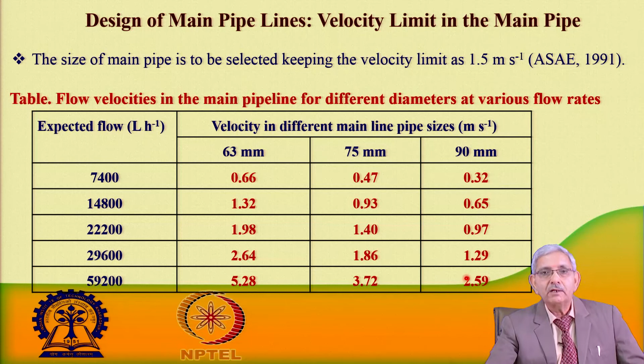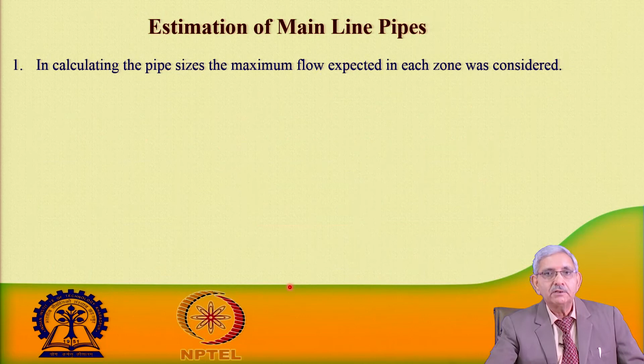For the 63 millimeter pipeline, we are getting 0.66 meter per second, and when we go for a higher flow rate, the velocity comes to this one. Now, when we go for a still higher flow rate, we find that the 63 millimeter pipeline will exceed the velocity limit of 1.5 meter per second. Then one should think of another pipe size, that should be a higher pipe size. Similarly, for the other pipelines, these are the values one can select by considering the velocity criteria.